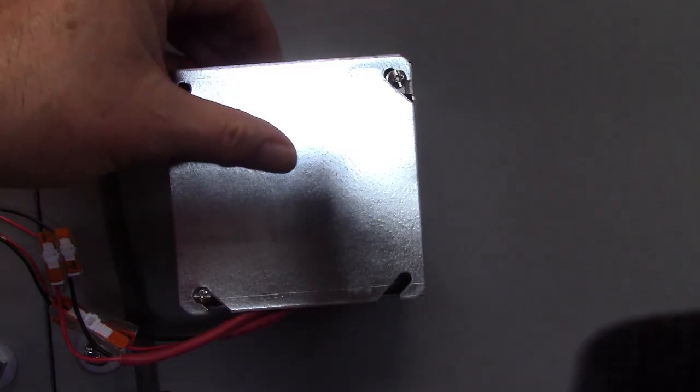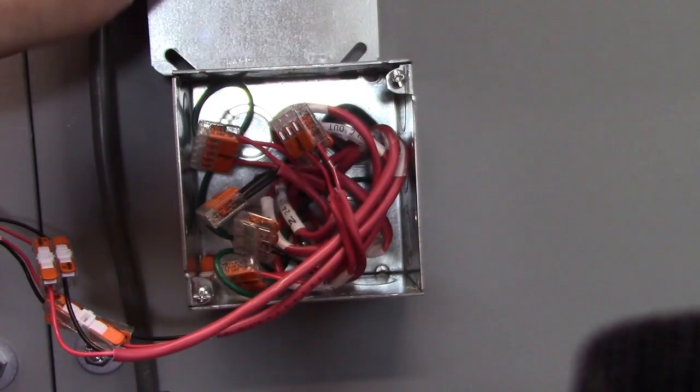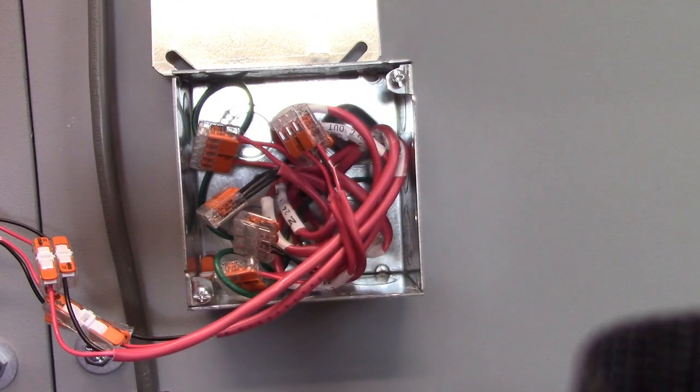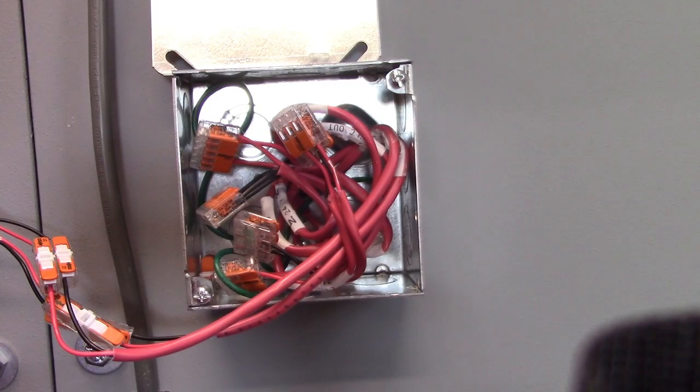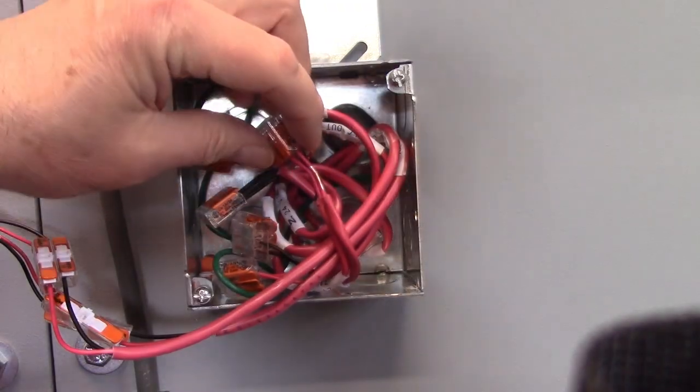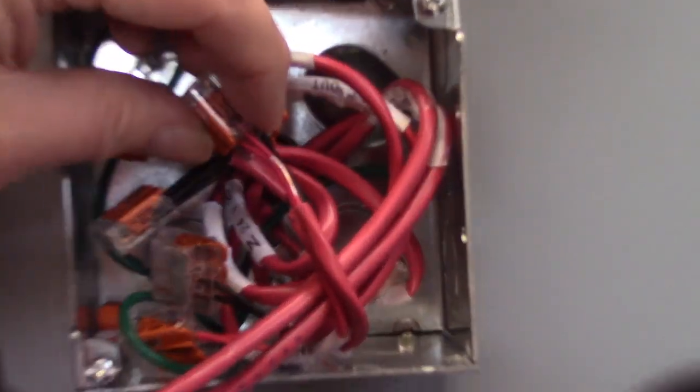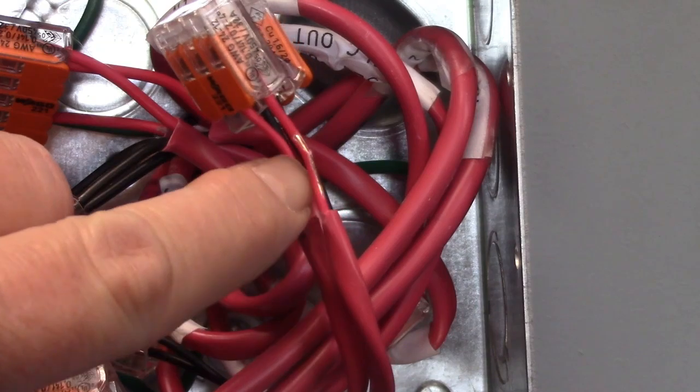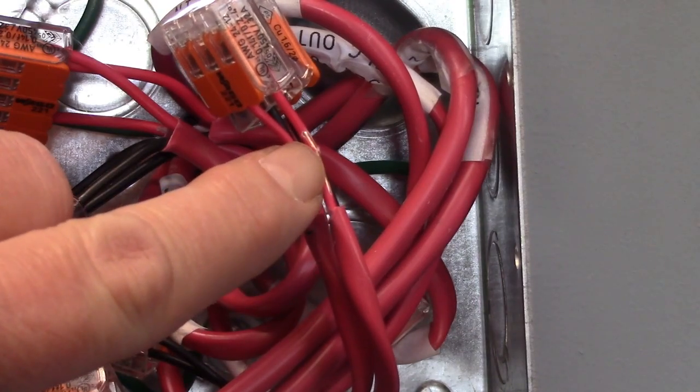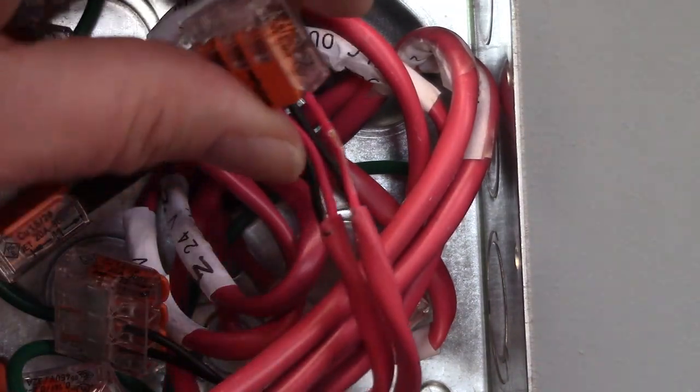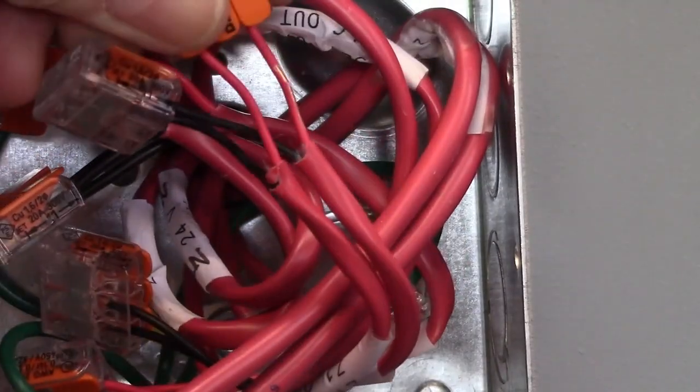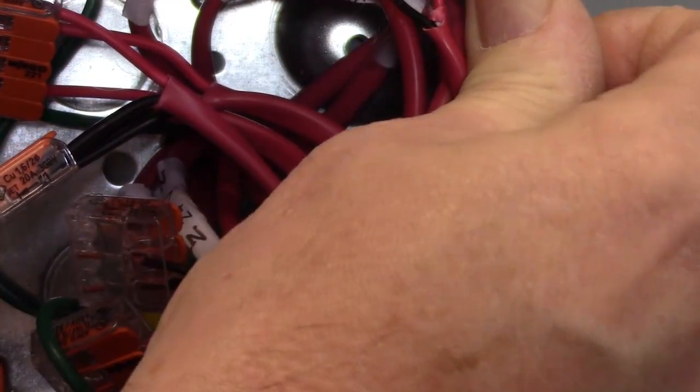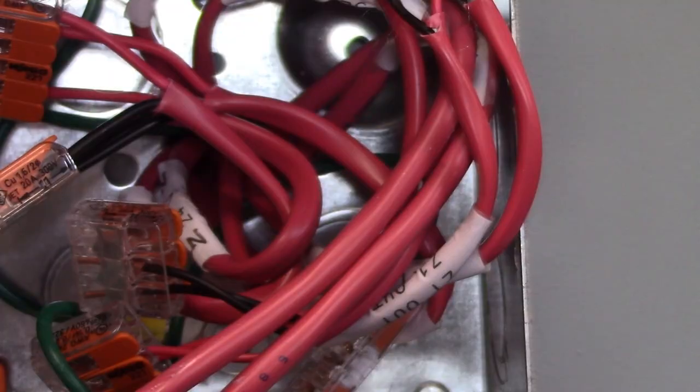So what can happen is inside of an electrical box or maybe above a ceiling where the wires are strapped to metal pieces of the building, if there's damaged insulation like you can see here, see there's bare copper right there. If that bare copper makes contact with the metal box, you'll hear the system start beeping that it's gone into ground fault.